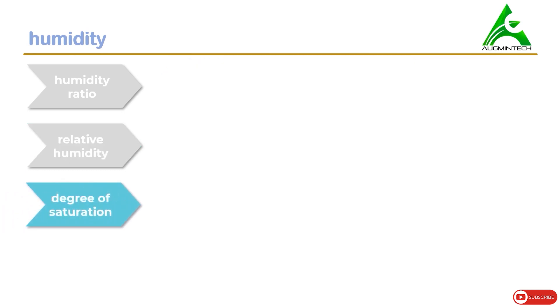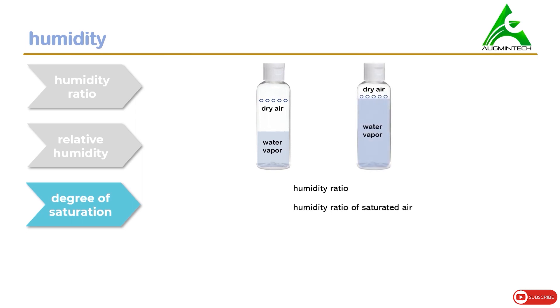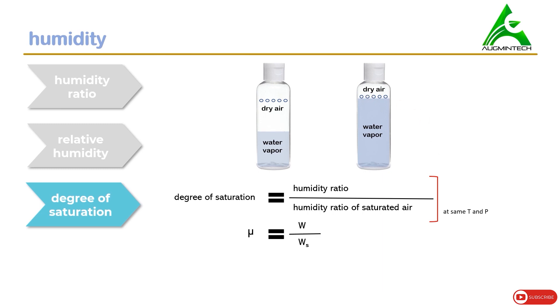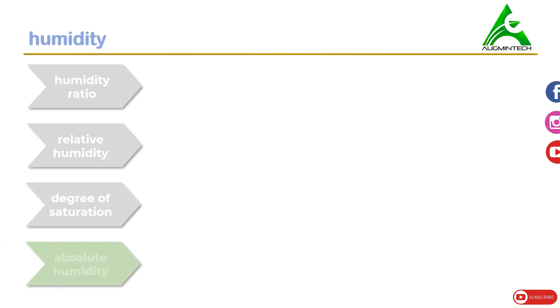Degree of saturation: to find it, find the humidity ratio of a sample of air, then find the humidity ratio of the same sample of air when it is saturated. The ratio of these two values gives the degree of saturation, and this must be at the same temperature and pressure. The holes on the two bottles are at the same height, so their maximum moisture holding capacity remains the same. Degree of saturation is written as μ = W / Ws, where Ws is the humidity ratio of saturated air.